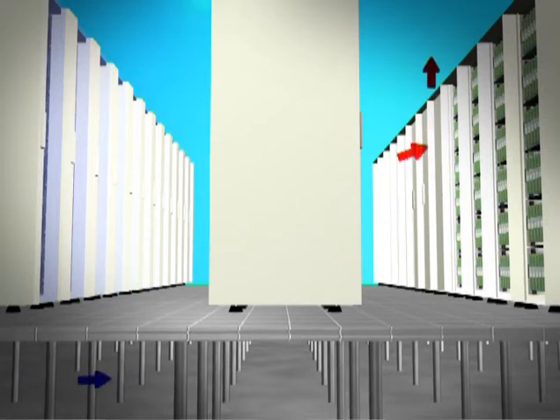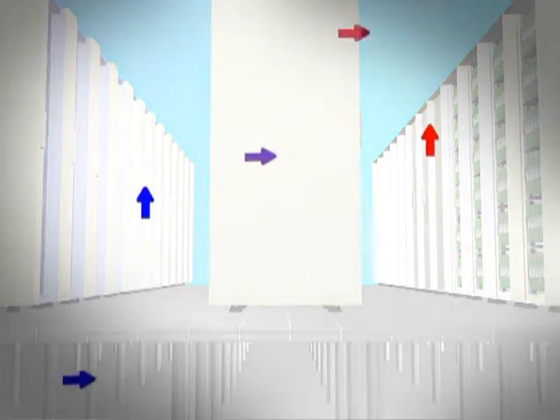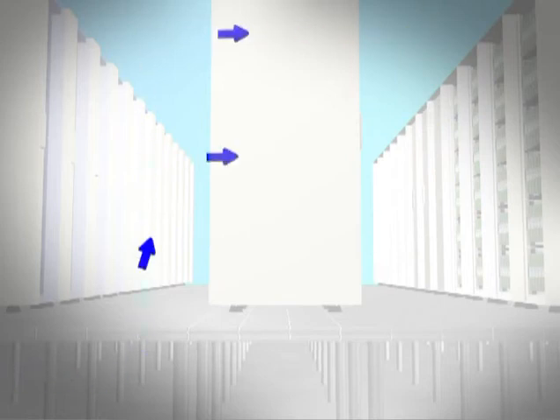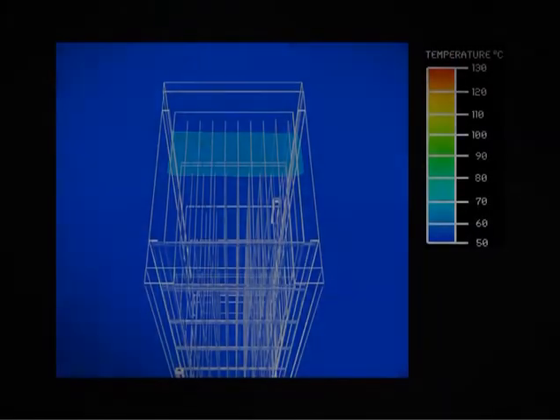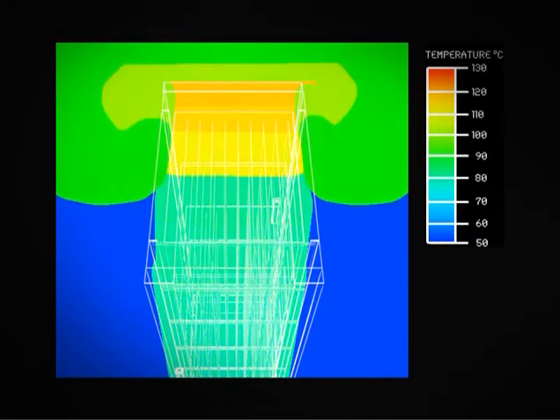Traditionally, data centers are cooled using the hot and cold aisle construction. External air conditioning units provide cool air to the front surface of the server. The server then pulls cold air from the cold aisle and exhausts the hot air into the hot aisle. However, hot and cold air can mix, and therefore this method isn't optimally efficient. More importantly, cooling capacity per cabinet is limited to about 5 kilowatts. Blade servers can no longer be supported using traditional cooling methods.